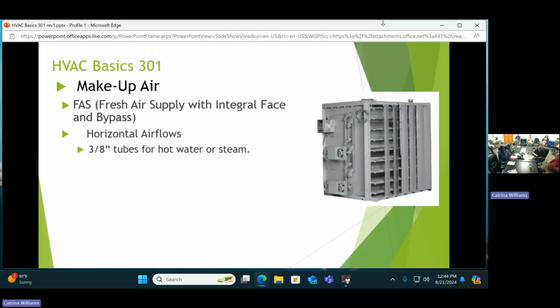One of the target areas that we go after with this particular makeup air unit design is boiler rooms, where there's one or more, sometimes 6, boilers in a room. Therefore it has dual actuators built into it. That's the motor that opens and closes the dampers. When this unit shuts off, we close those dampers on the entering air side and the leaving air side so there's no air blowing through into that boiler room, because there's smaller piping in there that can freeze pretty quickly. So it will isolate that cold air and keep it outside.